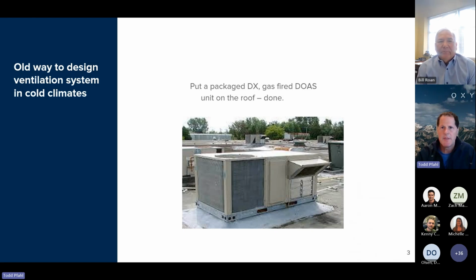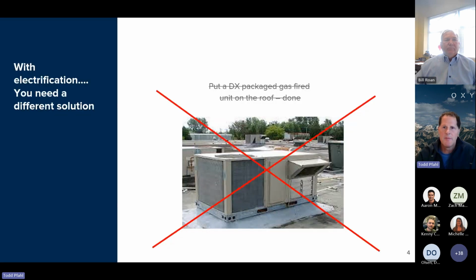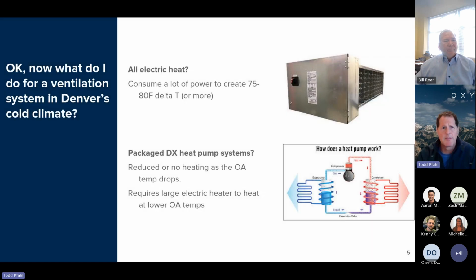So if we look at past designs to bring outside air or ventilation air into the building, we typically use package units located on the roof, whether that had 100% outside air or a combination of outside and return air. You use DX cooling for that side of things. And then on the heating side, you typically had a gas-fired heating element. Very simple, tons of installations around North America. As we move to electrification and decarbonization, we can no longer use the gas element for doing the heating. So we have to find ways of accomplishing this in other ways, particularly in cold climates.